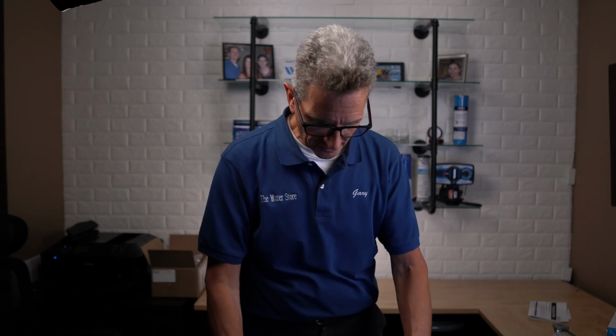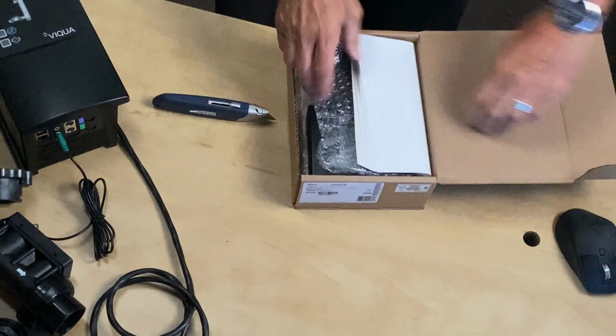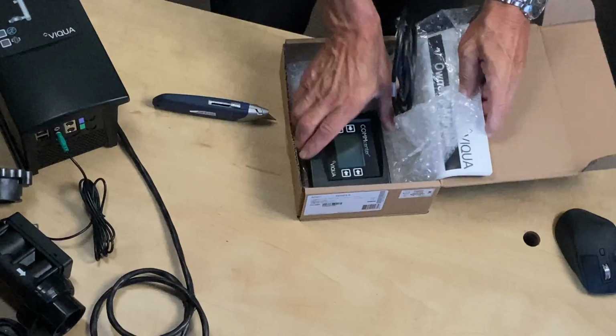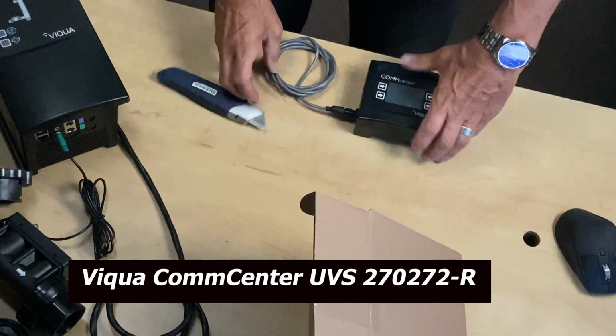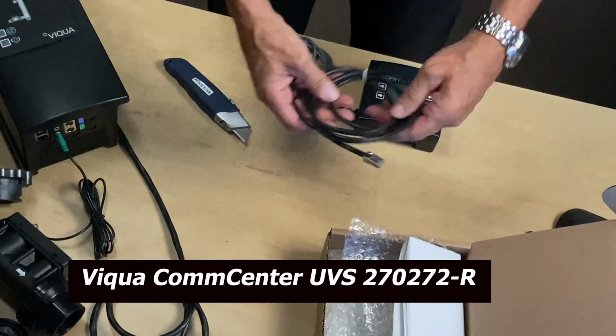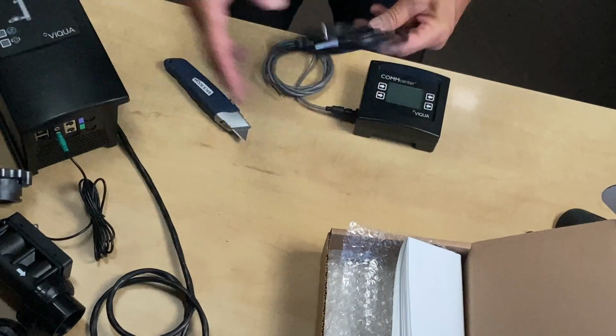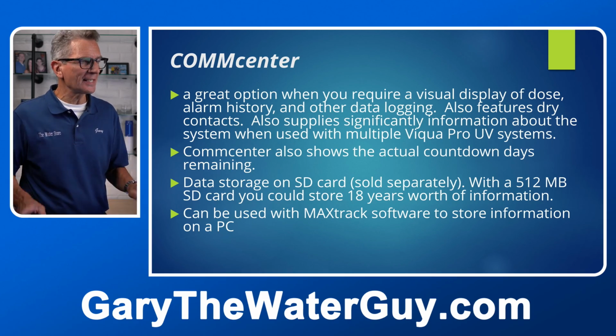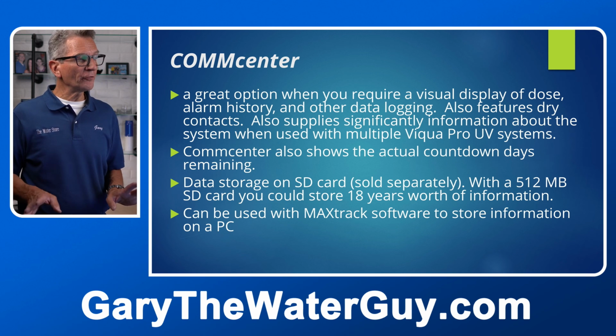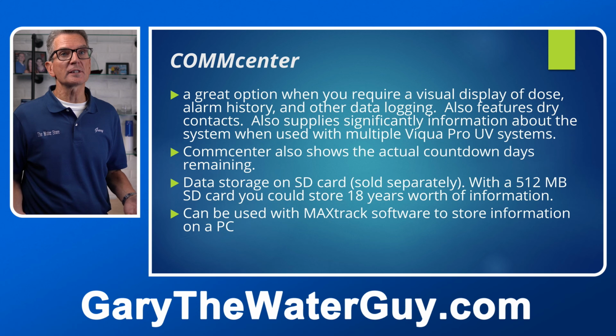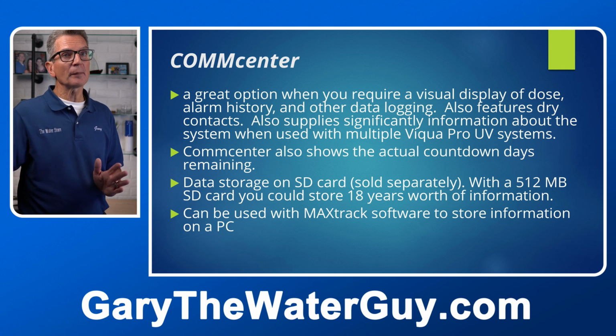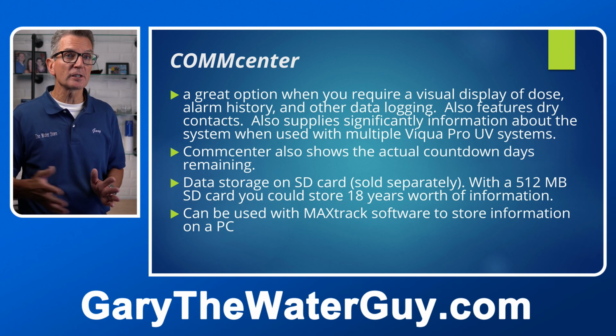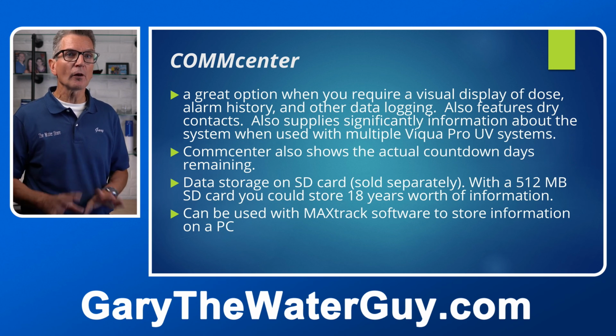So another optional extra I definitely like you to consider is the CommCenter. So we've got one here, so let's check this out. So this is the CommCenter here. And again, you can see the cable that comes with it that attaches it to the controller. So when it comes to the CommCenter, like it says here, it's a great option when you require a visual display of the dose, the alarm history, and other data logging. It also features dry contacts. Also supplies significant information about the system when used with multiple Pro UV systems. So again, you have one CommCenter and you can connect up a bunch of these ultraviolet disinfection systems to it. I believe it's up to 6, and you can monitor it all through one CommCenter.